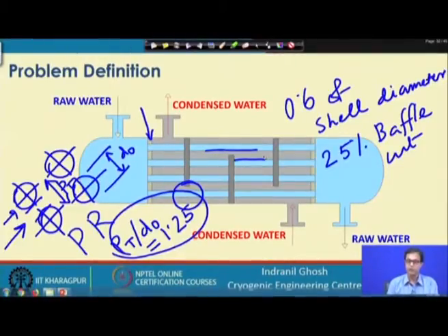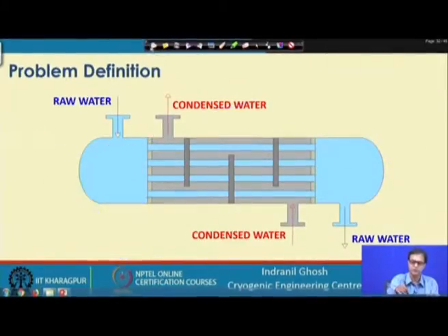So, accordingly we have to slightly over design the heat exchanger, and it should never be more than 35%. So, we have to take into account that, considering the foul resistance, our design should never be more than 35% over designed. So, these are the specifications which are given.